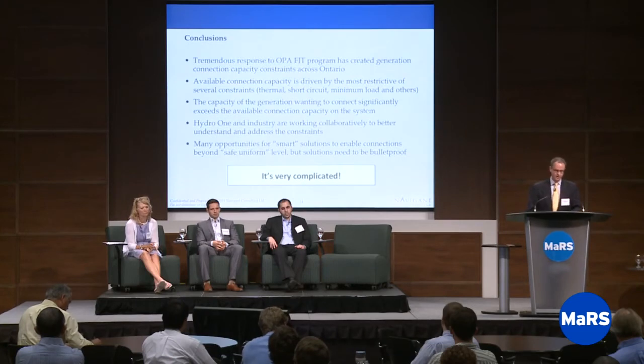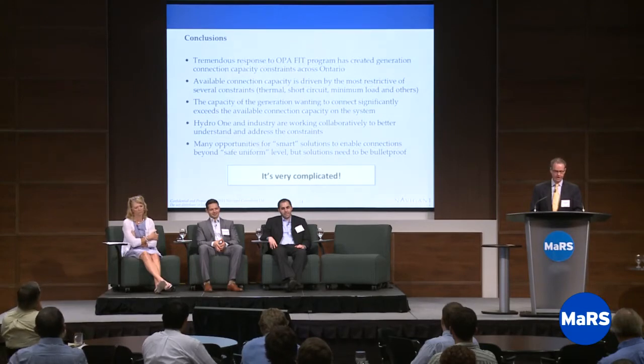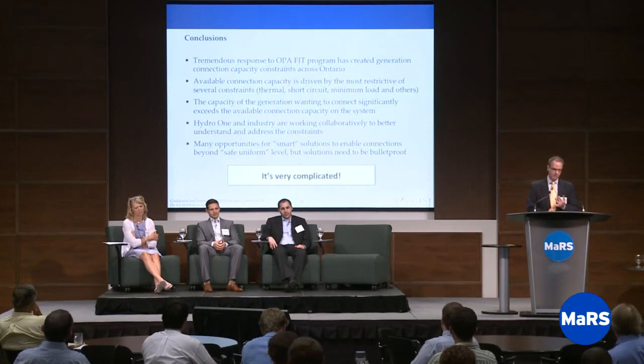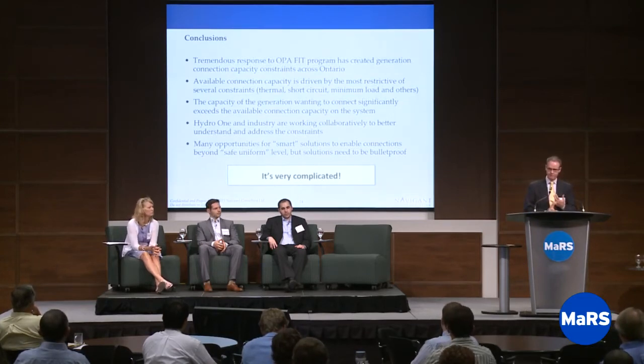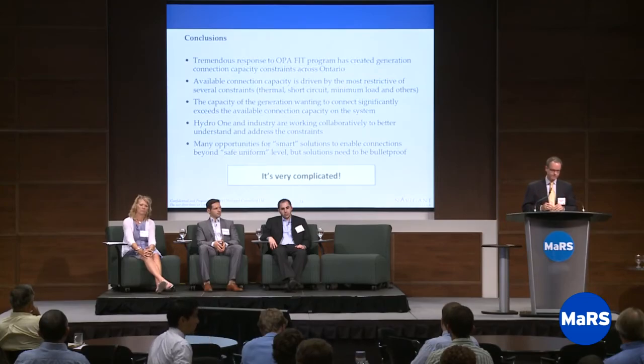So in conclusion, there has been a tremendous response to the FIT program. It has caused, and is creating, some generation constraints. Typically, those constraints are driven by the most restrictive of generally three factors: thermal load, short circuit (fault current), and minimum load, and there are others, and they sometimes work together in weird ways.